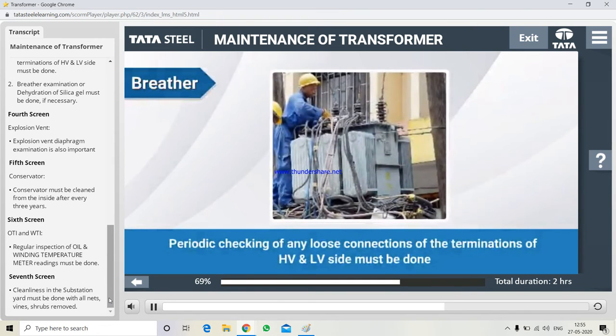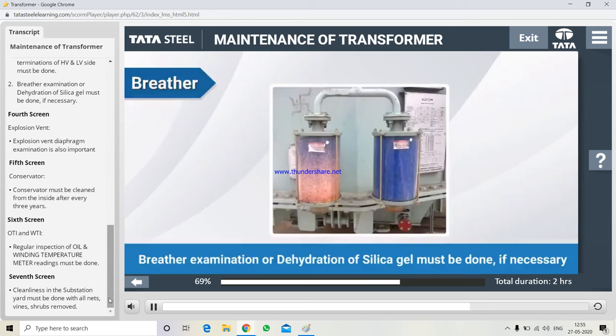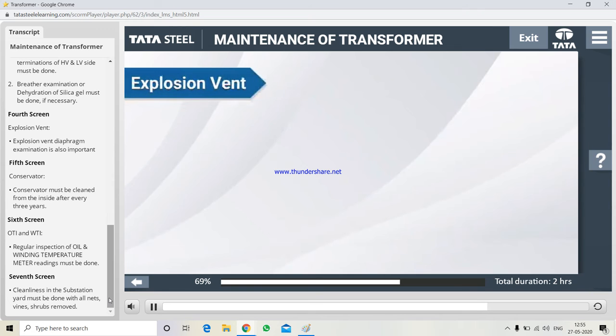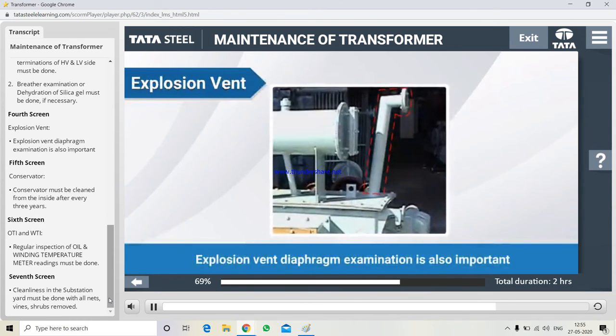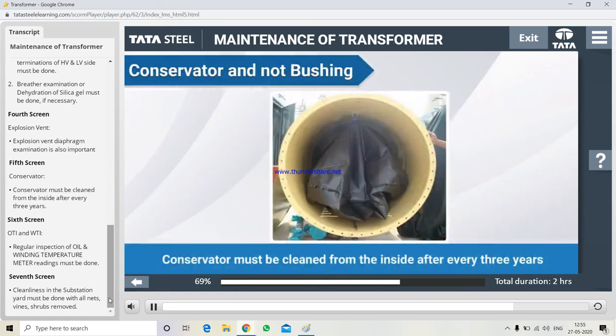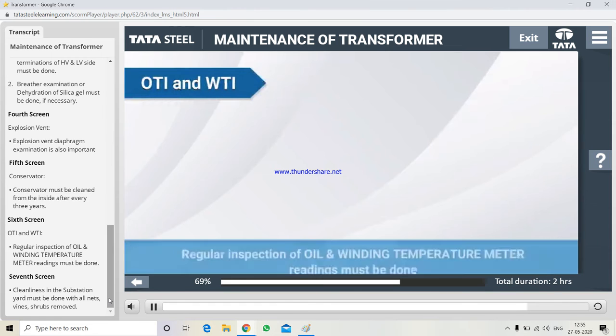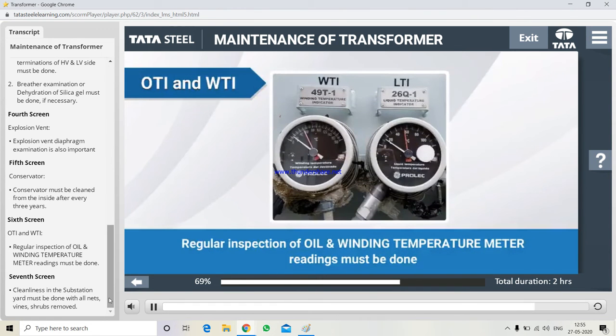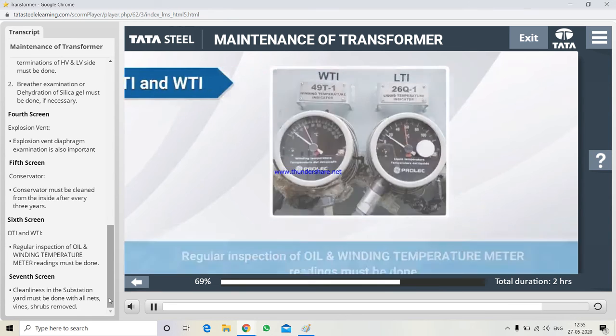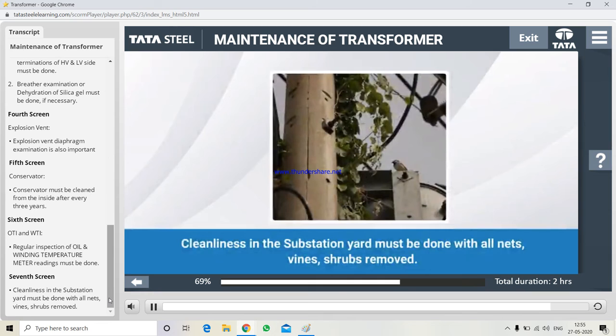Periodic checking of any loose connections of the terminations of HV and LV side must be done. Breather examination or dehydration of silica gel must be done if necessary. Explosion vent. Explosion vent diaphragm examination is also important. Conservator. Conservator must be cleaned from the inside after every 3 years. OTI and WTI. Regular inspection of oil and winding temperature meter readings must be done. Cleanliness in the substation yard must be done with all nets, vines, shrubs removed.